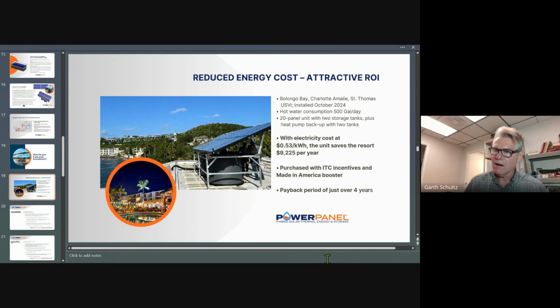Incoming cold water gets preheated in a recirculatory loop unto itself. Then once a client demands it, through a shower or a spigot in their hotel room, it goes through the heat exchanger sets circulating through the rest of the hotel, through the heat pump. So we provide to that heat pump system as much thermal energy as is being produced by the PVT system.